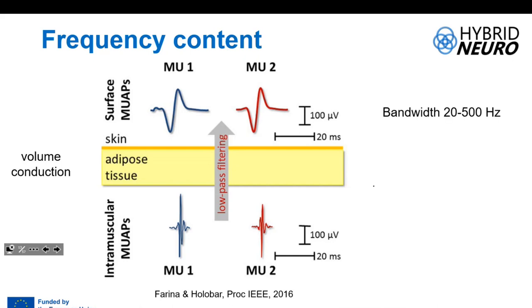So if we record surface EMG, the bandwidth is between 20 and 500 Hz, and we usually use a sampling frequency of 1 kHz. While if we place an electrode within the muscle and record the intramuscular signal, the bandwidth is actually higher than 1 kHz, because these signals are much spikier, and as a consequence we need to sample them at a much higher frequency.